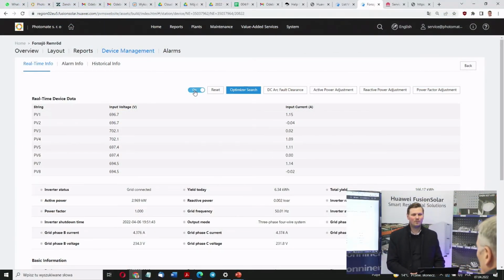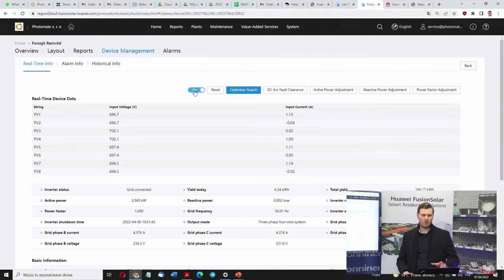We have to turn it on or off for some specific time. What do we need? It's actually available here. Can you use some contact, a relay, remote contact? But how would you like to control this relay? So it's possible, of course - what do you need? Each inverter has 4 digital inputs which can be used in different ways. One of the ways is to trigger a shutdown or startup of the inverter. So it's possible to do it like this if you have some relay which is remotely controllable. It's possible, of course.